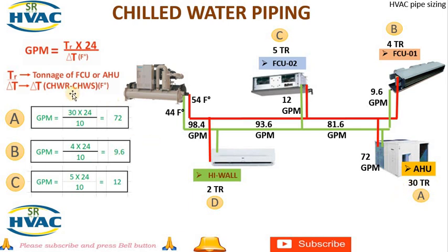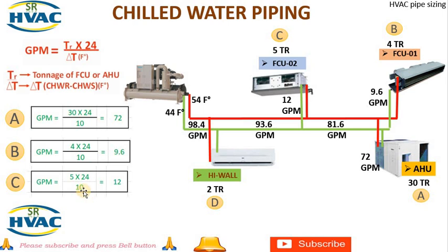For the AHU, the capacity is 30 tons. Applying the formula: 30 × 24 ÷ ΔT, where ΔT = 54 − 44 = 10°F, gives us GPM for the AHU = 72 GPM. For FCU1, with capacity 4 tons: 4 × 24 ÷ 10 = 9.6 GPM. For FCU2, with capacity 5 tons: 5 × 24 ÷ 10 = 12.0 GPM.